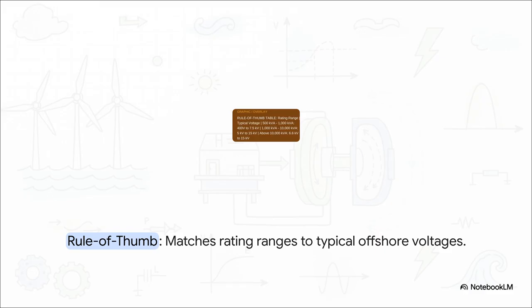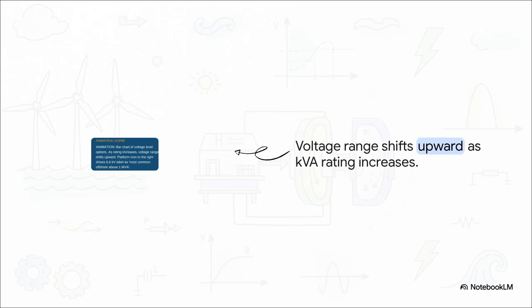Notice how your system rating completely dictates your voltage range. If you're generating somewhere between 500 and 1000 kVA, you're generally sitting between 400 volts and 7.5 kilovolts. But watch what happens as that power demand grows. Between 1000 and 10,000 kVA, the floor shifts up to 5 kilovolts. And once you jump above that massive 10,000 kVA mark, you are exclusively looking at the 6.6 to 15 kilovolt range. You can really see here how, as the kVA rating increases, that practical voltage range absolutely must shift upward. Why? Well, because massive currents generate massive heat. By stepping up the voltage, you drop the current.